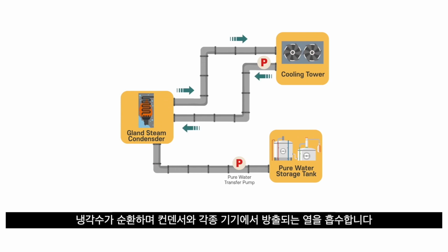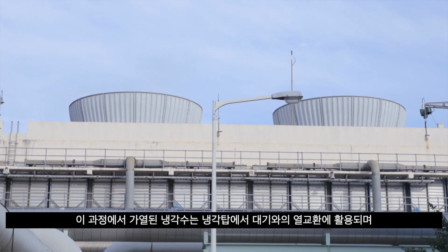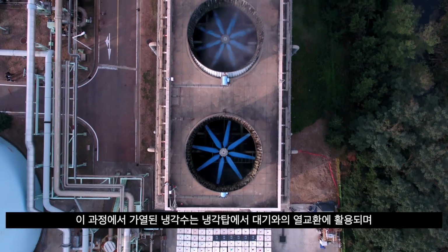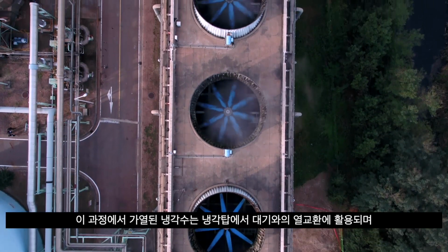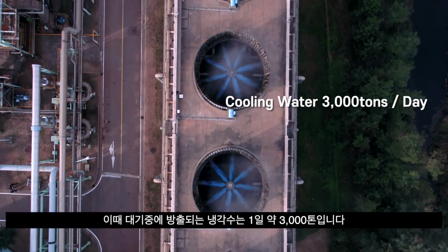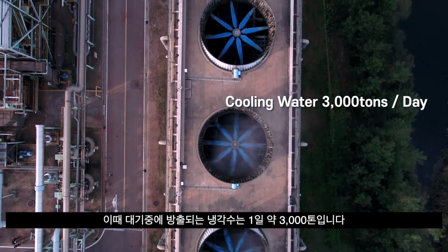Heat emitted from the condenser and various other devices is absorbed through cooling water circulation. Water is circulated through the condensers and other devices, whereupon it absorbs heat and helps to keep the equipment cool. A cross-flow evaporative cooling tower is used to transfer heat from the cooling water to the atmosphere, and in the process, around 3,000 tons per day of cooling water is discharged into the air.